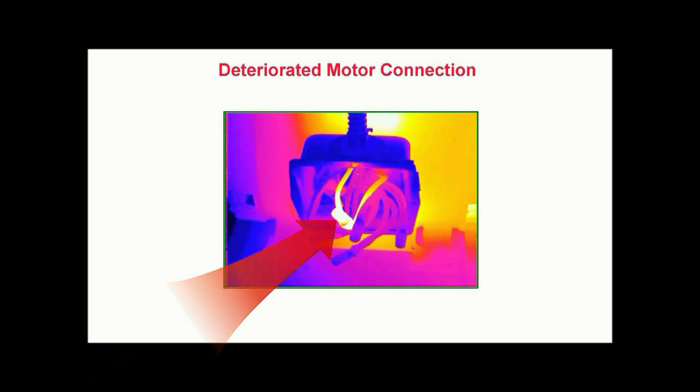Here we see a thermal pattern caused by a loose or deteriorated electrical connection within the junction box of a motor. Since thermal imagers cannot see through solid materials, the junction box cover has been removed to provide a clear line of sight to the connections.